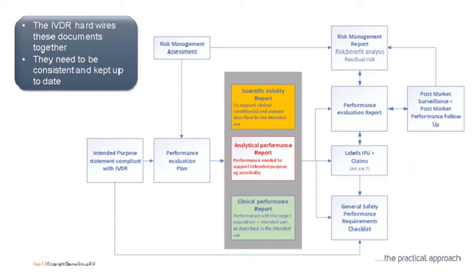So the performance evaluation plan, if you have a legacy device, will be describing where information you already have, maybe from a 510K, maybe from a PMA, maybe from your existing IVD directive technical file, where it's all going to come from. And then you need to prepare a scientific validity report, an analytical performance report, and a clinical performance report. Now, the issue here is if you make a mistake in your intended purpose, you will have a hole in your performance evaluation plan, and then each of the supporting reports. Ultimately, these are all going to be drawn together into a performance evaluation report, so that will also be incorrect.